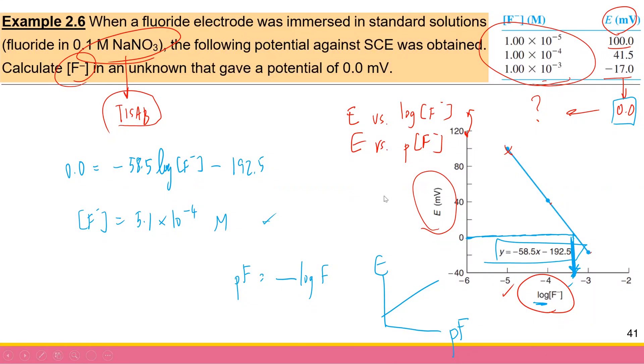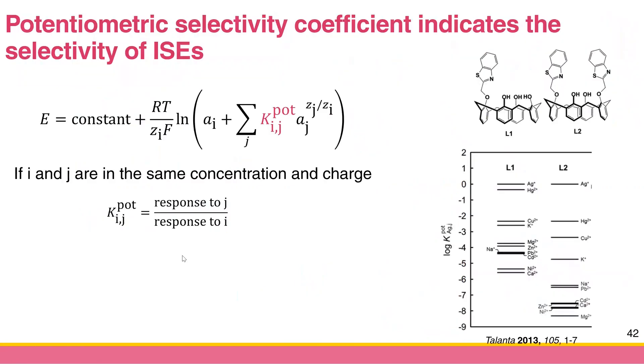All of this assumes your electrode only responds to one kind of ion. In real life, your electrode may respond to several kinds of ions. For example, the glass membrane electrode may respond to sodium in addition to protons — sodium becomes an interference. There are ways to quantify such interference using something called the potentiometric selectivity coefficient.